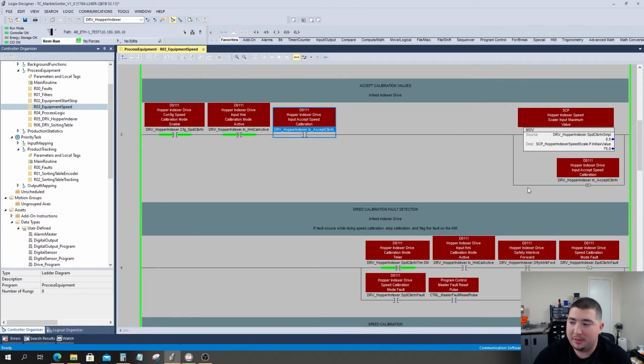So the whole purpose of having speed calibration is to know that you definitely have the axis rotating at the speed that you have designated. If you don't know your relative speed and you're just guessing that it's correct, then you may run into issues when you try to get the axis to move at a specific speed and it can't achieve it because your scaling is off by some order of magnitude. So often in controls, a very good practice is to have a way for the PLC to be given an official actual speed so that what you have in the program matches reality, because very often the outside conditions are never so precise.